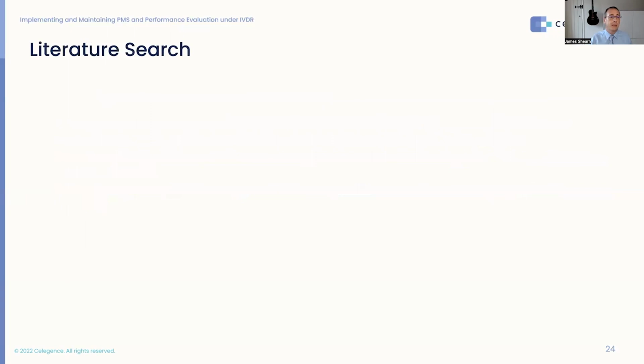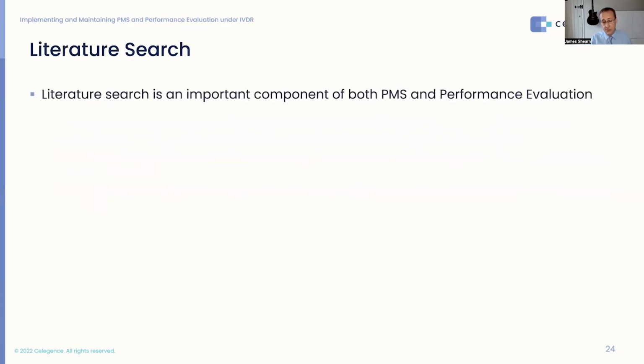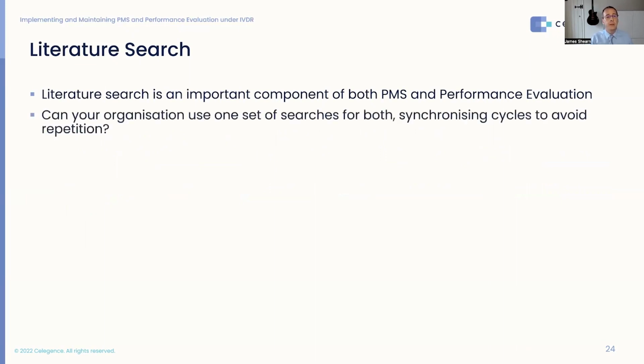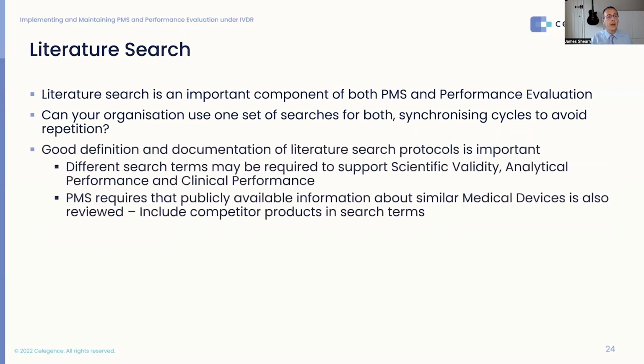Now, let's talk a little bit about literature search as a component of this. Literature search is a very important component of both post-market surveillance and performance evaluation. One of the questions to be asked is, updating of the performance evaluation is required on an annual basis for a Class C or a Class D device, and you're required to update your PMS as well. So can your organization use one set of searches for both, synchronizing the cycles in order to avoid repetition? Good definition and documentation of literature search protocols is important. You might, for example, require different search terms to support your scientific validity, analytical performance, and clinical performance.